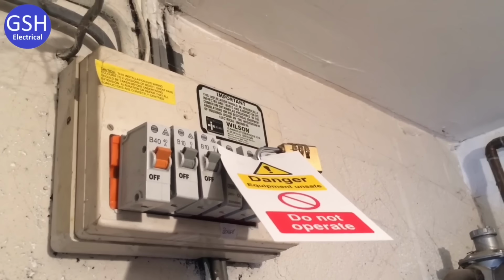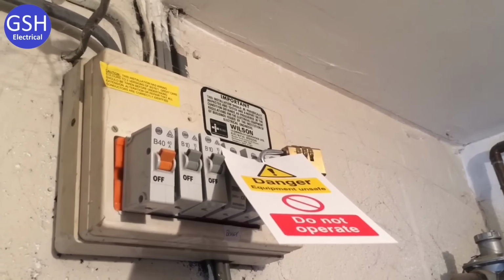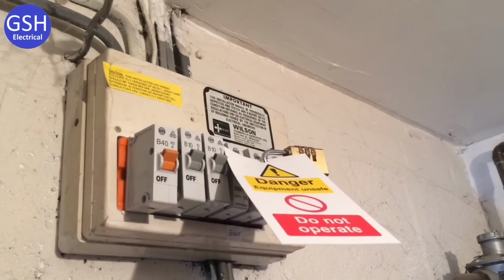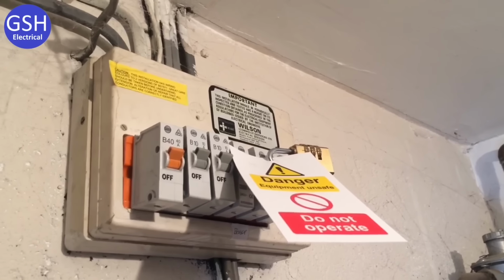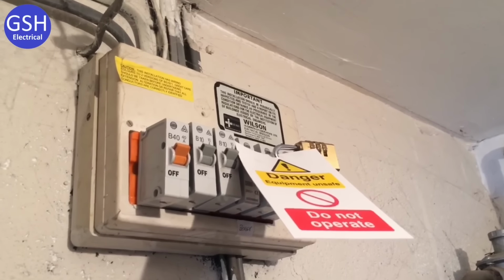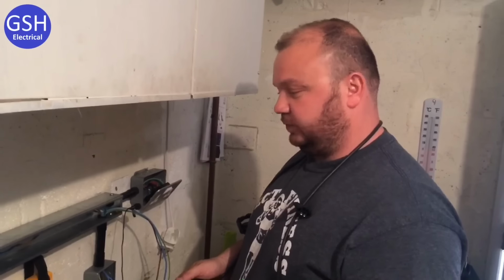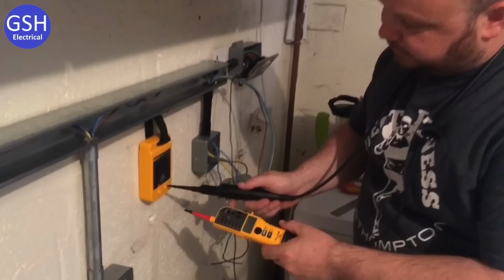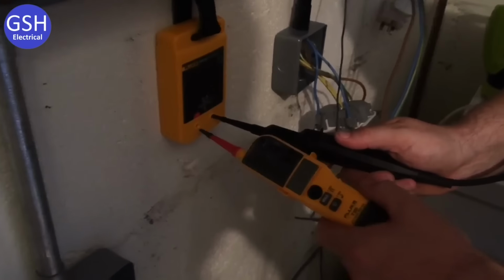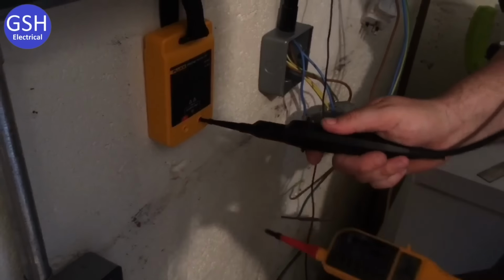Okay, so we've locked off the circuit breaker that we're working on. We believe it's dead because we used the plug-in voltage indicator, but we're still going to prove the back of the socket using our approved tester and our proving unit in the next stage. So you're going to prove the back of the socket is dead using your approved voltage indicator. What are we going to do with it first? I'm going to check it's working with the proving unit. Yeah, that's all good.